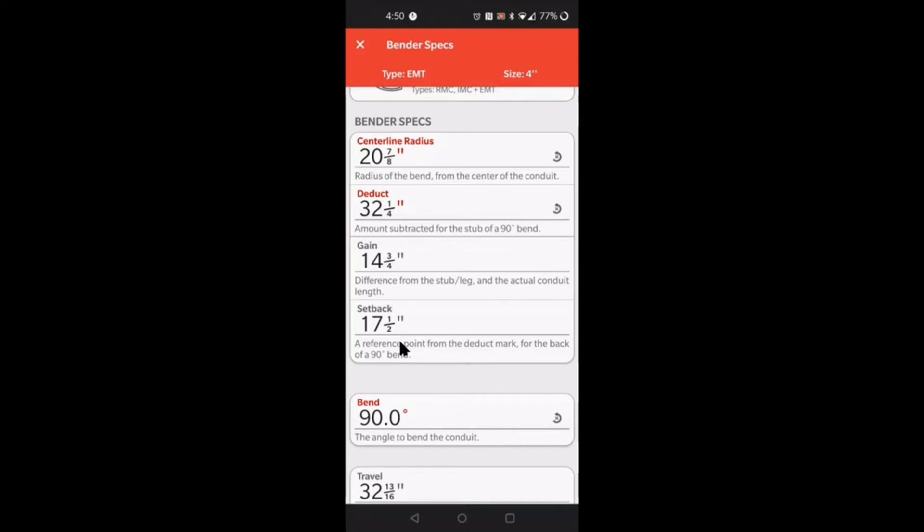Very simple, you can lay out both marks without having to bend the 90 and take it out and then measure from the back of the 90 to make your second mark for the kick. You don't have to do that. What you can simply do is lay out your 90 degree bend. Let's just say you wanted a 40 inch stub. Basically you take your 40 inch stub and you deduct 32 and a quarter, and that leaves you with seven and three quarters.